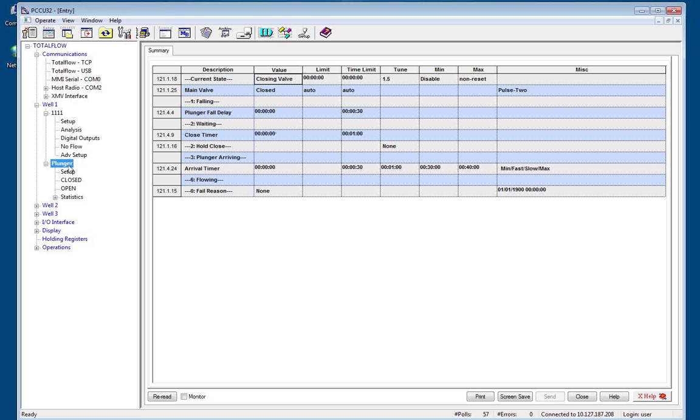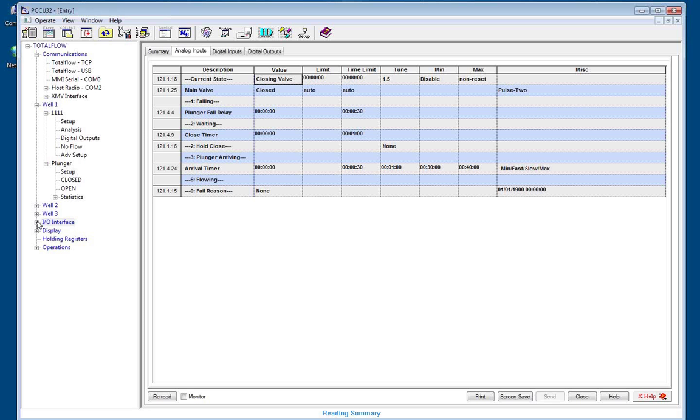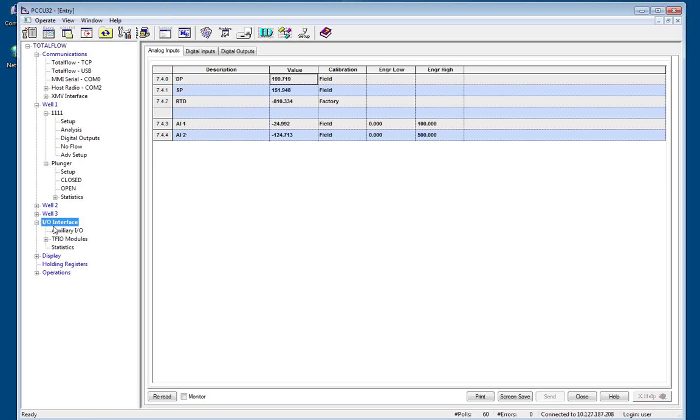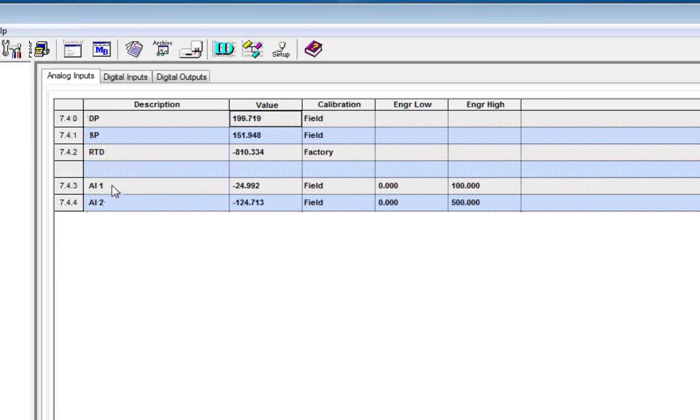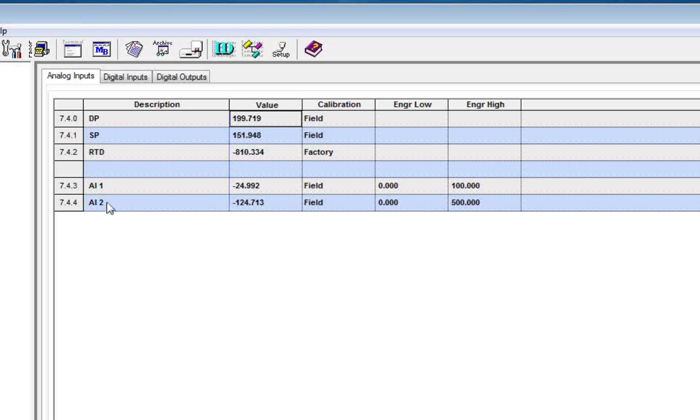Now that comes into play as we go through and set up I.O. for plunger lift. Remember we said that I.O. interface was in application 7. So as you can see, my raw AI's for this meter is in 7.4.3 for AI1. AI2, 7.4.4, the physical location within the software of where that I.O. is.